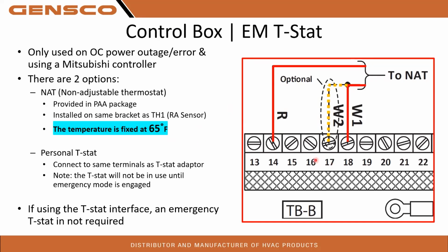You are going to wire that on the TBB terminal block between red and W1. If you have a two-stage gas furnace, you'll just do a jumper between W1 and W2 to bring on that second stage right away. Again, both the thermostats will be installed into the return air of the system. And make sure you do not flip those thermostats around, because once again, like I said, you will come up with an error code. Also, if you are using a 24-volt thermostat, once again, you do not need that non-adjustable thermostat.